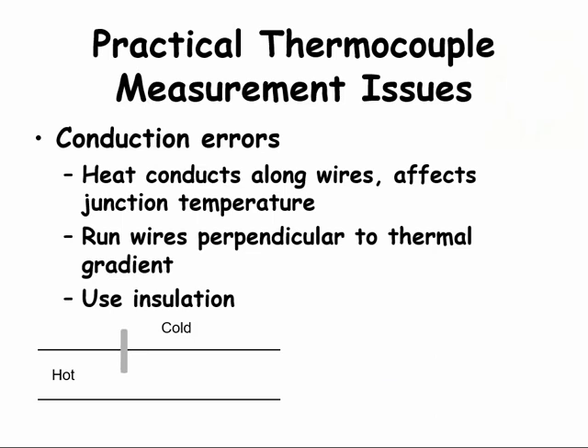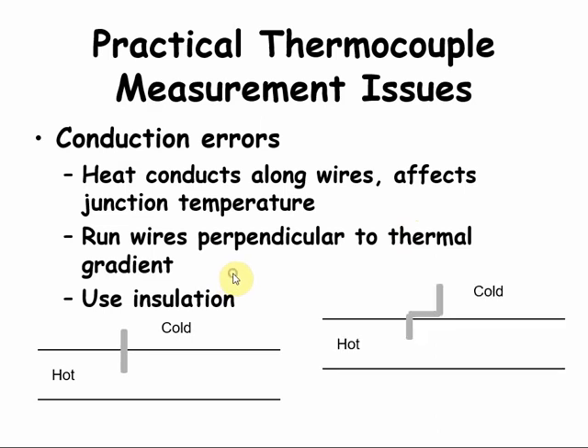Another practical temperature measurement issue is related to conduction errors. Conduction errors occur when a temperature sensor crosses a hot zone and a cold zone. If the measurement device conducts heat, and the thermocouple wire and many other temperature sensors do conduct heat, the heat conducted will cause errors in the temperature measurement. The heat will raise the sensor temperature a bit, or the cold will cool the sensor a bit. The two ways to mitigate conduction errors are to insulate the pipe or duct to reduce heat exchange, or to have a wire run parallel to the duct so that the wire gets warmed along the duct. These are issues when very precise temperature measurements are required.